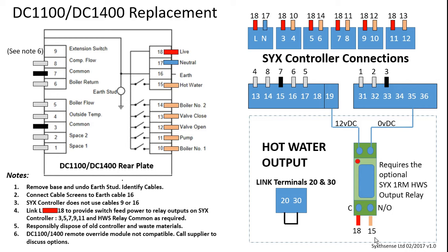At this first step, it's worth noting that the cables should be identified. If they're not identified with cable numbering, make sure that you take the moment to put your own identifications on those cables. You're going to be pulling those cables around, you're going to be moving them. Identification tags may fall off, so make sure you're fully happy about the tagging of the cables so that you can be confident that you're going to put the right cable in the right place.